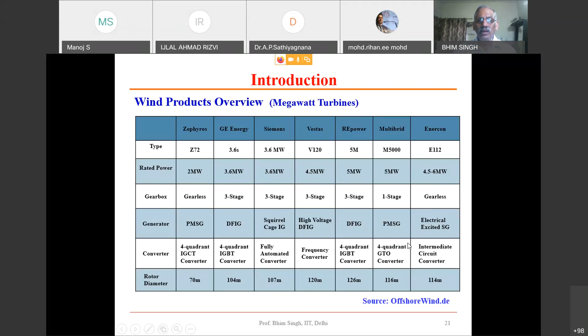They are also gearless when using a conventional cylinder pole synchronous machine. However, you will find many using a single stage gear. But if you look at DFIG, which is a 3-stage gear, or squirrel cage machine with double converter, or even DFIG with double converter - all these machines use a double converter. But of course, in DFIG, the converter rating is smaller compared to all these others.